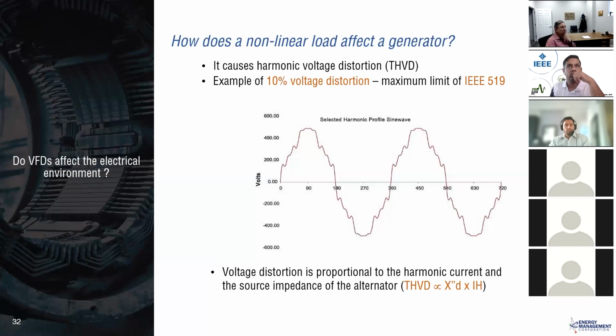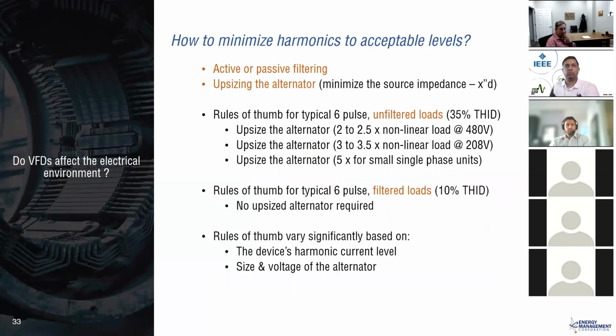We can also come across one more thing: if a motor is connected to the alternator, it is connected in parallel, which reduces the impedance. But the motor being small in size, that consideration is not significant. So that's the reason we don't consider adding the motor's impedance in parallel as a significant thing. Moving on. As I already discussed, these are the ways that we can reduce the harmonics: active or passive filtering, and upsizing the alternator.